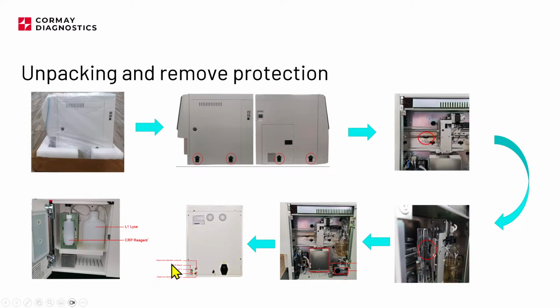On the back of the analyzer, we have the power connector. There is also a sticker here which says please remove those binding clips from the inside of the analyzer first, and then connect the power. We also have the reagent tubes connection and waste connection. According to the colors, we have diluent, lyse for hematology, waste connection, and there will be 2 sensors connected also on the back. These need to be connected before you turn on the analyzer.